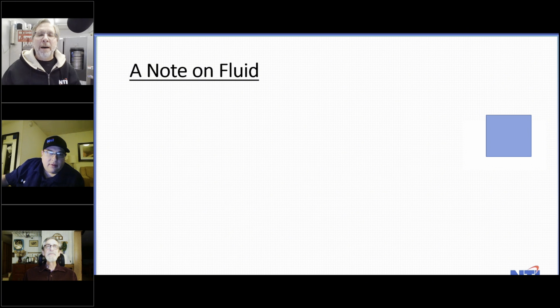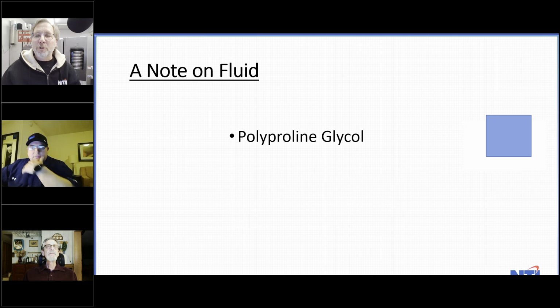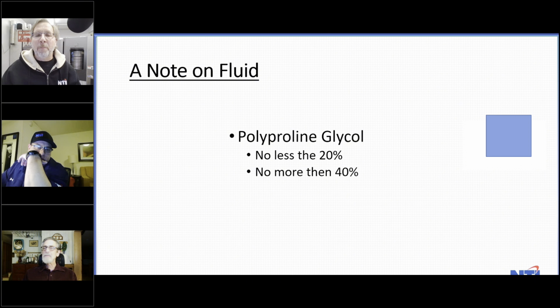A note about fluid: use polypropylene glycol - that's probably spelled wrong. No less than 20%, or it becomes unstable. In my humble opinion, no more than 40%, because that will give you down to -60 burst protection. I aim in my area in Pennsylvania for about 25%, and I still have guys putting 50% in. With that, your pumps are going because they think it's molasses compared to water, and it's horrible heat transfer. Not only is it thicker, but it doesn't carry or transfer the heat as well.